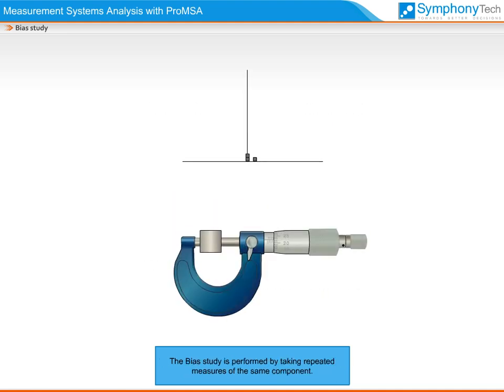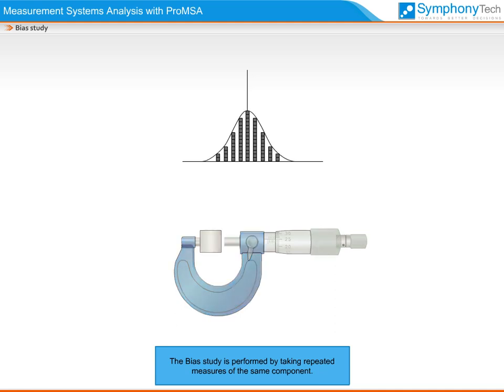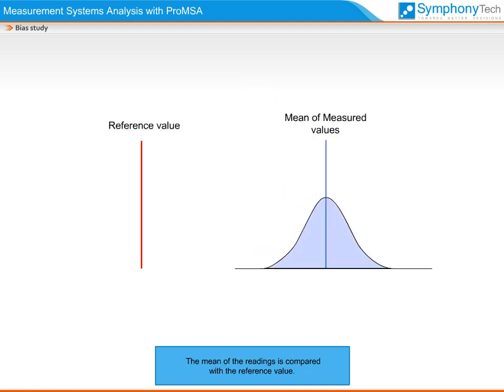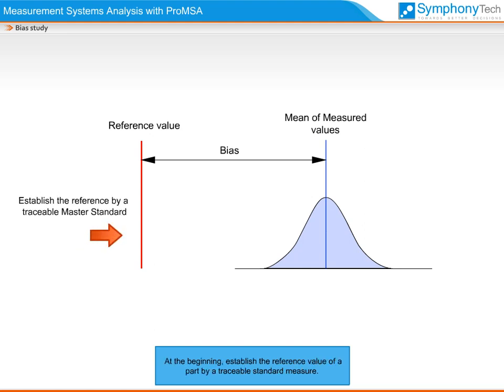The bias study is performed by taking repeated measures of the same component. The mean of the readings is compared with the reference value. At the beginning, establish the reference value of a part by a traceable standard measure.